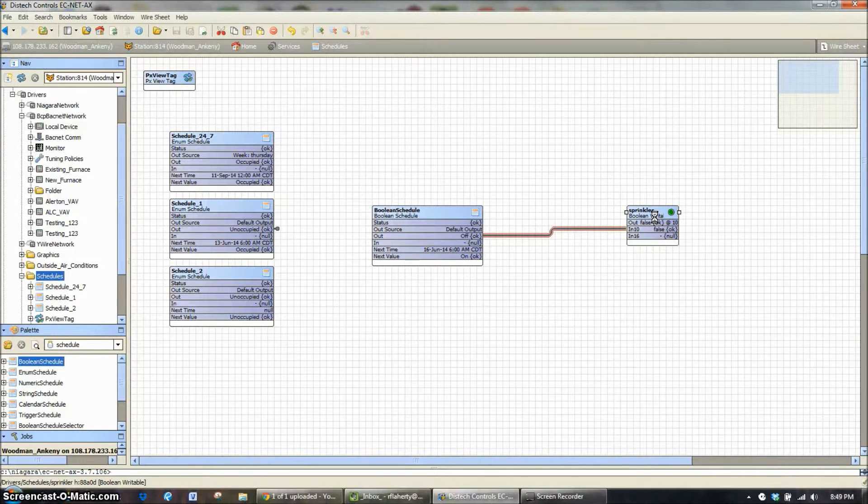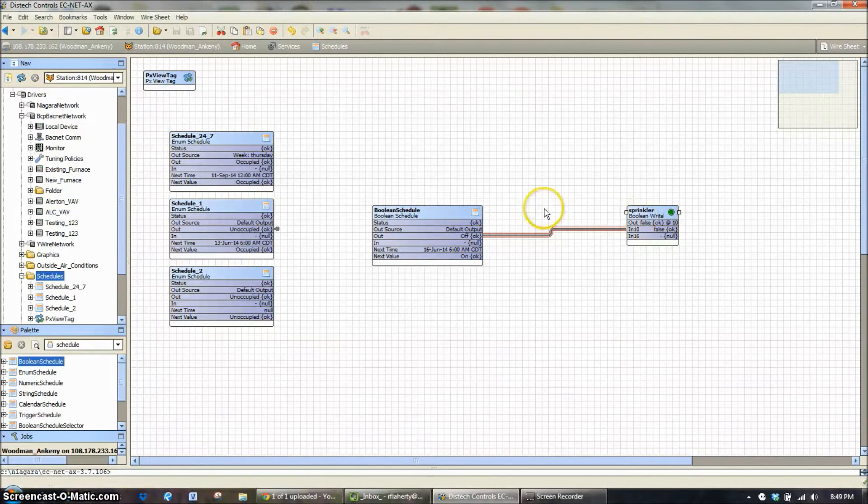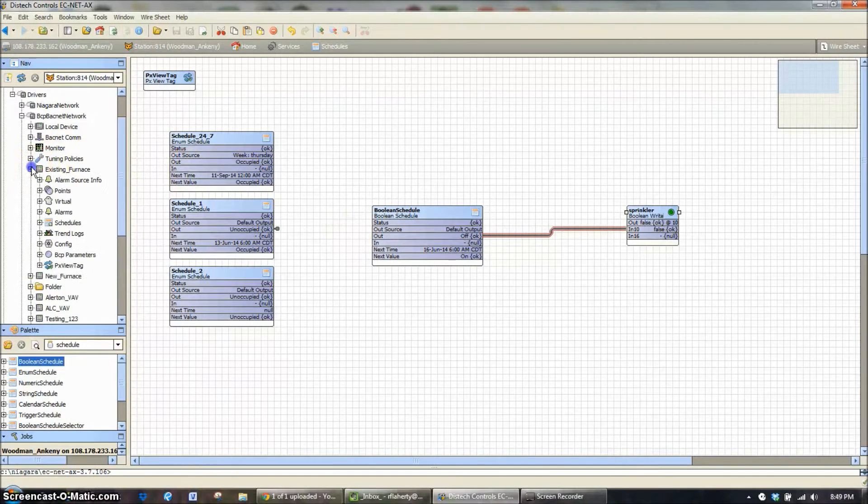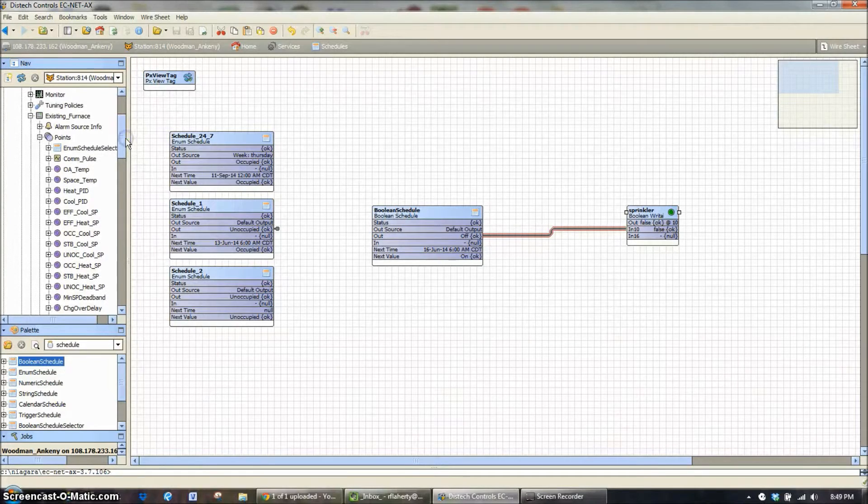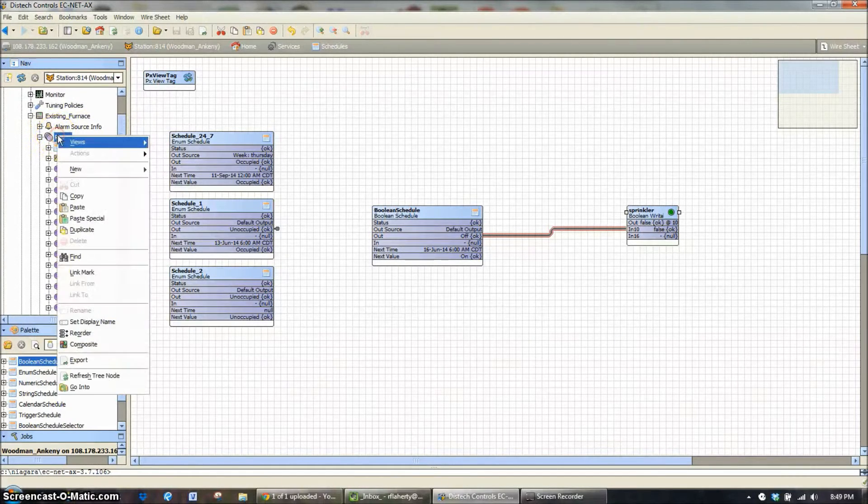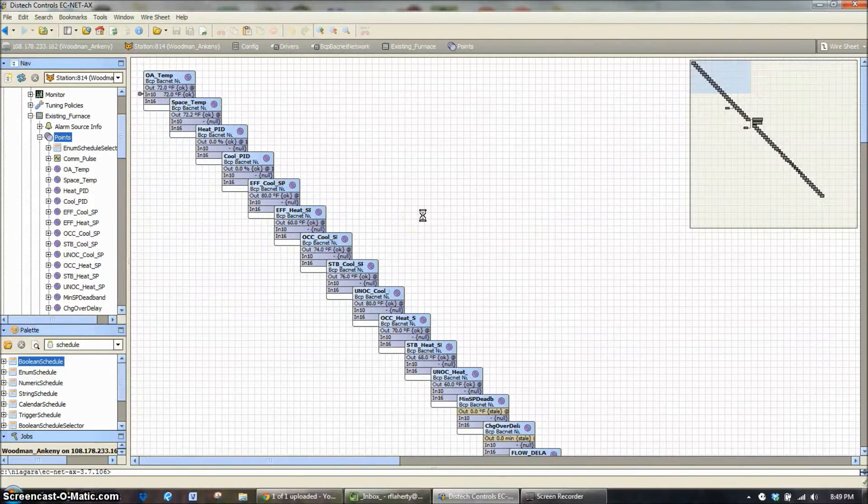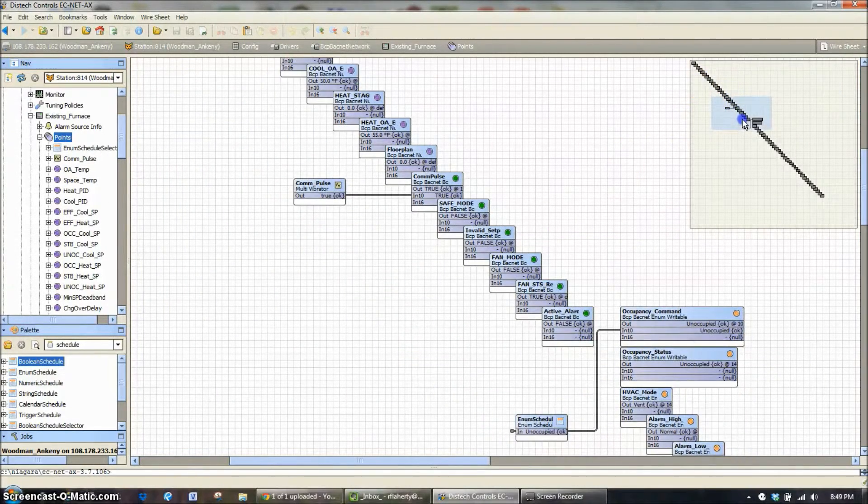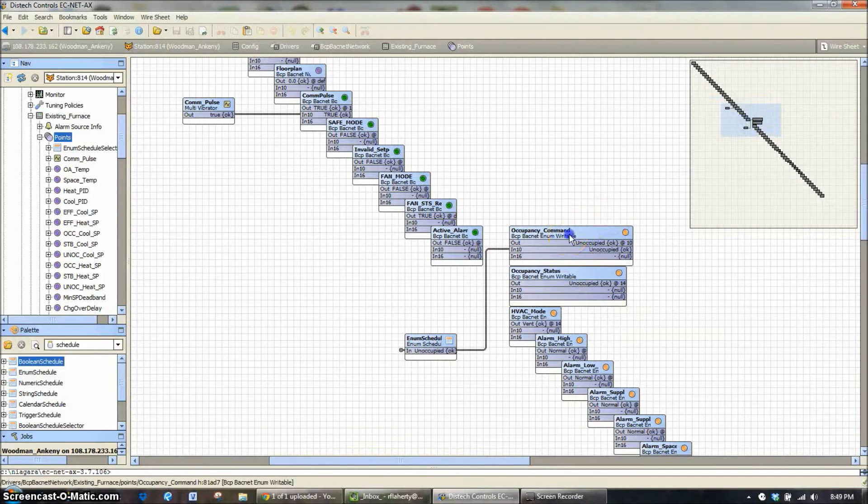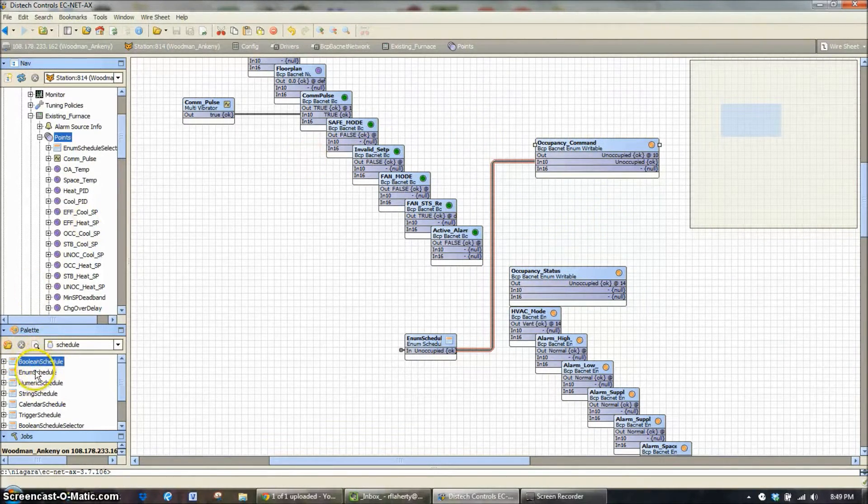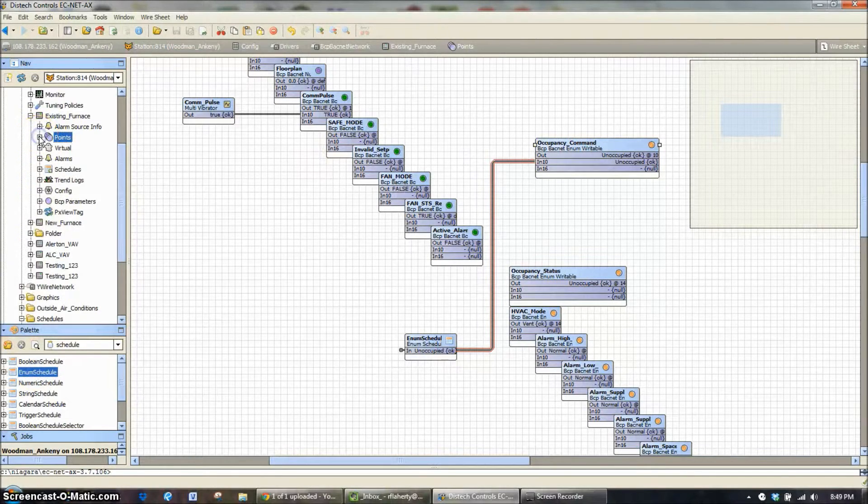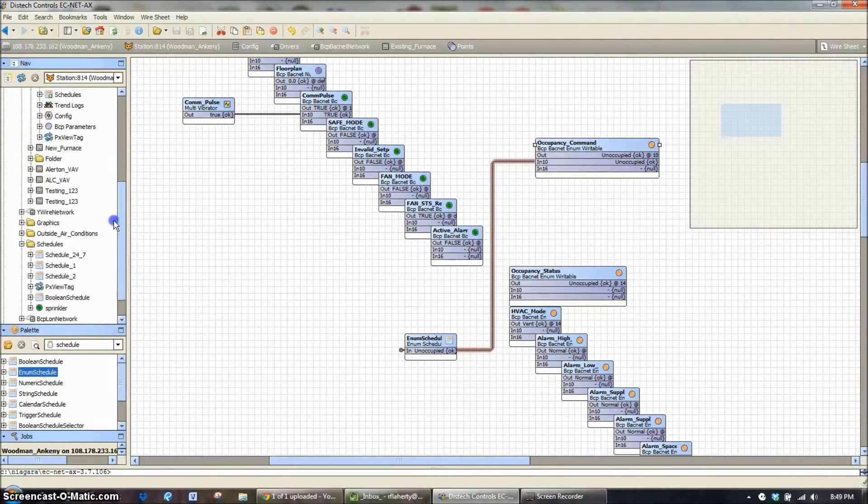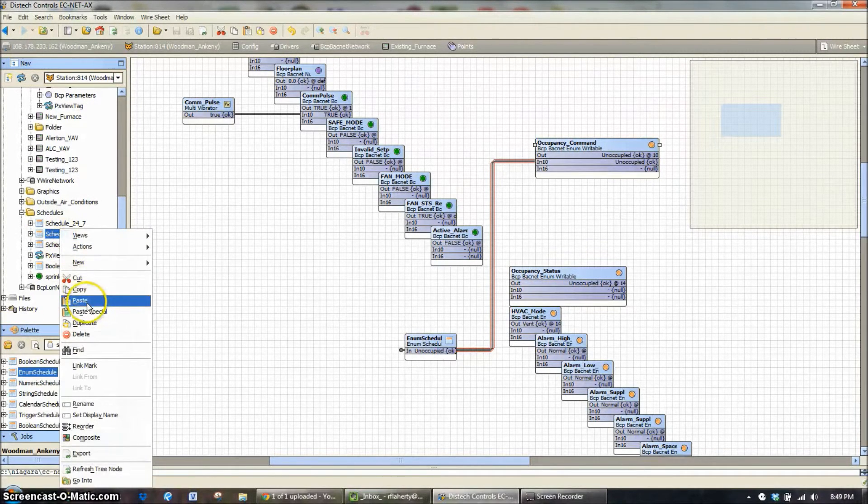And right there we've created a Boolean schedule tied to our sprinkler. If that was a physical point on a controller, it would turn on and off on that schedule. That's how you would add a schedule to a sprinkler. Now, one more thing that we want to touch on really quickly. If you have a room that you need to run on a much different schedule than everything else, you can see in all of the zones, we have them set up to where they tie back to those main schedules for the whole building. If you have one that needs to run much different than all the others, you can create an enumerated schedule.